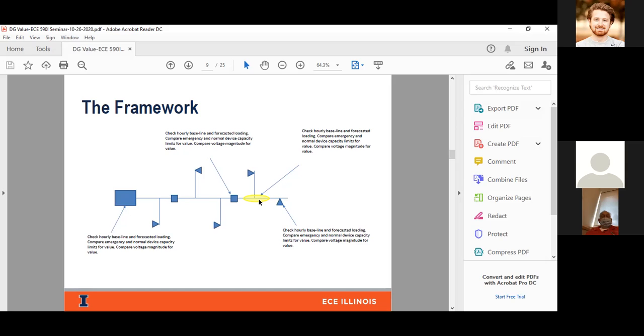If you look at that yellow bubble, and let's say there's a violation at this device here. I don't know if you can see my cursor, but it's this square here. Any DG installed downstream of that square, if that square was seeing a violation, is going to help or potentially help improve the violation. So you will see value for DG for anything downstream of it. Anything upstream of it, however, is not going to contribute value to that specific asset. So you'll probably see 0 value for any DG installed upstream of the violation.